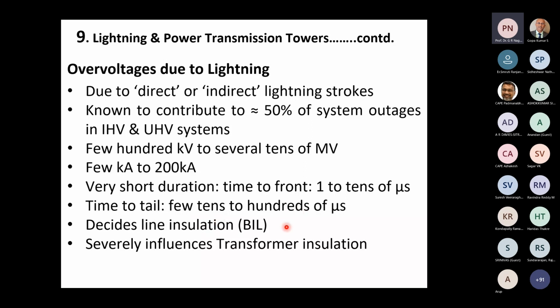As I told you, the distance between the overhead ground wire and the phase conductor is to be such that a stroke to the overhead ground wire should not cause a flashover from the overhead ground wire to the phase conductor itself. That means it actually becomes an invitation to lightning to the phase conductors. As we go further, you will see how the line insulation, that's the line insulators for 220 kV or 400 kV, is to be designed. We'll see it later, because this is very critical: it influences the transformer insulation, which means the entire power system.